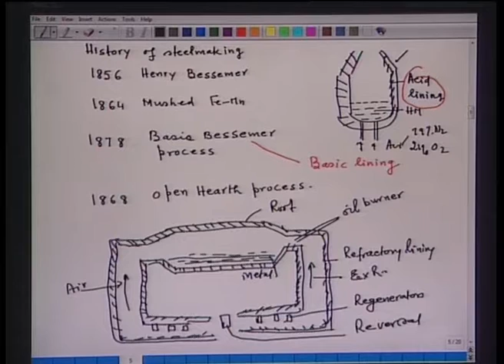These are the so called regenerators. Regenerators were used to preheat the air, and here was an air valve. This is the valve for reversal. That is, in one cycle, here goes preheated air, then here go exhaust gases out. So, one regenerator is on the heating side, another is on the cooling side. When on the heating side, preheated air passes through this and exhaust gases go through the other outlet. So, that was the whole idea of employing two regenerators.